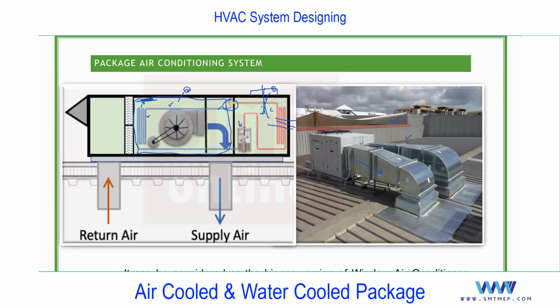So in the right side image, since it's air cooled, you see this fan is used to cool the condenser, this side. So this side is the condenser side, the high side, and this side is the low side. In that you'll find the evaporator coil and a fan. And this we can call the supply duct, and this we can call the return duct. And how can you identify this? Remember, the supply duct compared to the return duct is smaller in size.